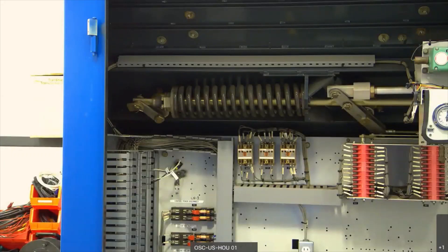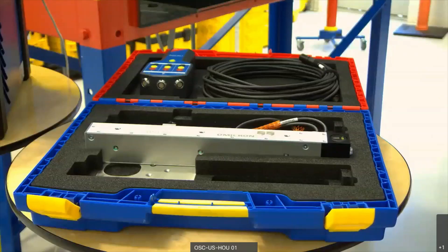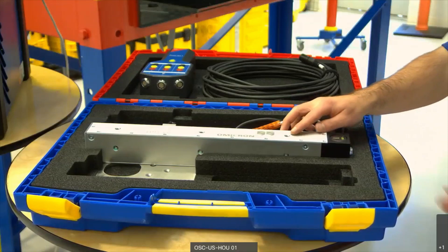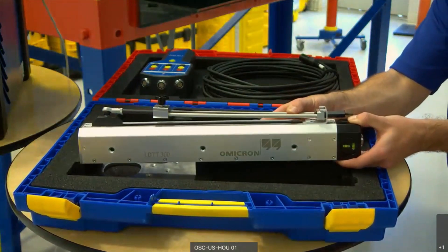Our first step is always safety, so we want to ensure the breaker won't operate as we mount the transducer. We can verify this by checking the spring and seeing it in a discharged state. This is the transport case for the LDTT 300. Within it is the transducer itself and some tools we use to mount it.